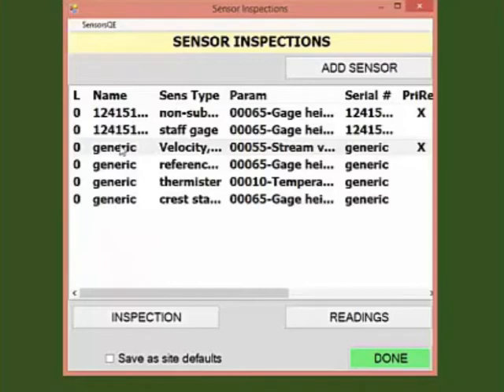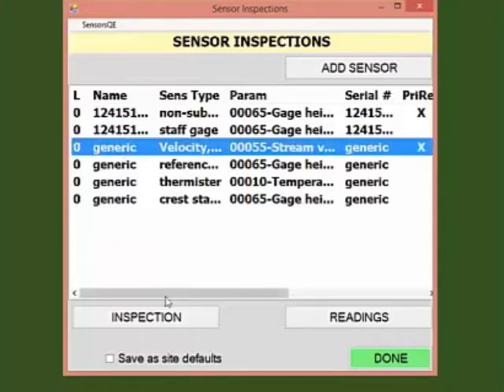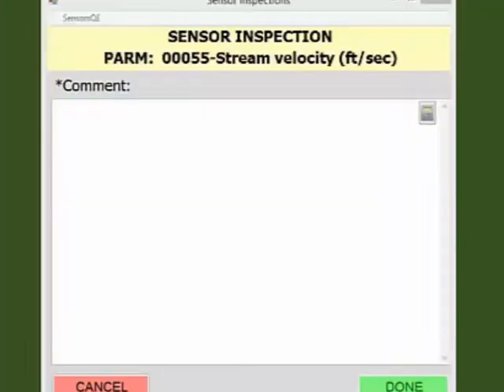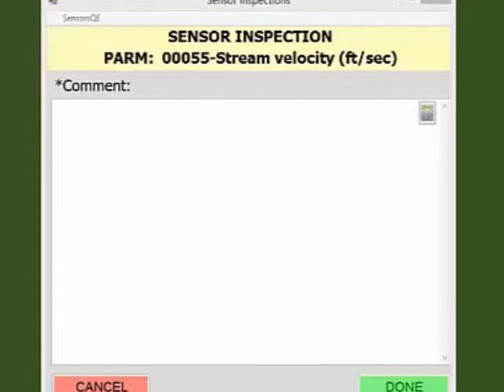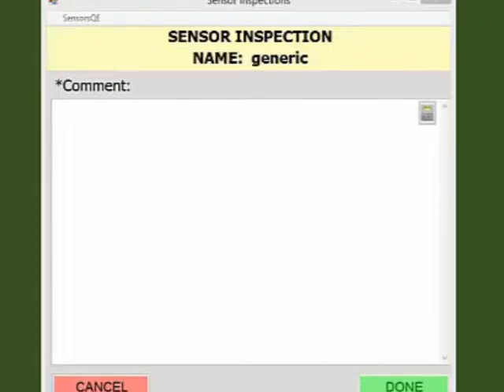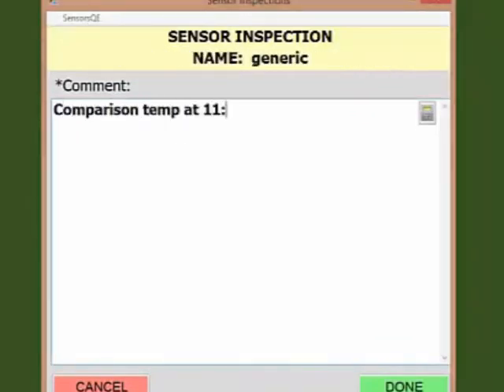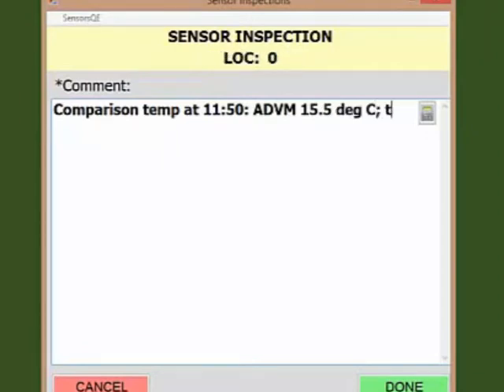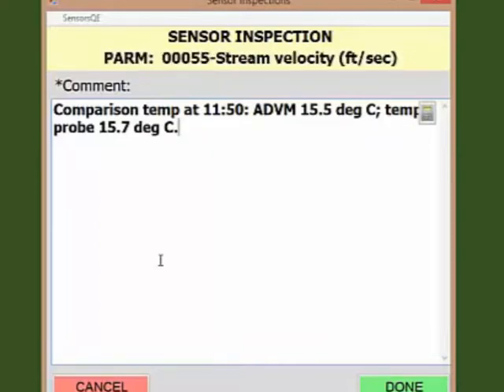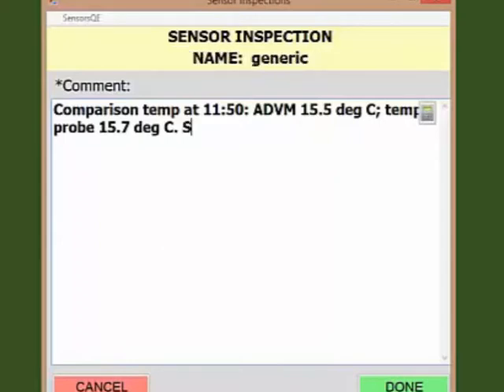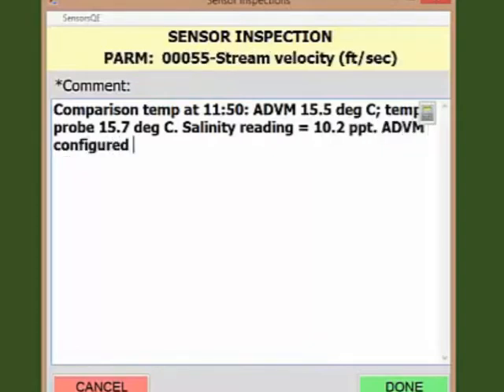Highlight the velocity sensor in the Sensor Inspections table and click Inspection. Per OSW policy, we need to perform a temperature comparison with a thermistor in the ADVM. Let's enter notes about the temperature readings from your ADVM thermistor and a comparison temperature probe. The comparison temperature reading must be made close to your ADVM and the two temperatures must match within 2 degrees C per OSW memo 2010.07. I did my temperature comparison next to the ADVM and I'm going to write: comparison temp at 1150, ADVM 15.5 degrees C, temp probe 15.7 degrees C. If your index velocity stream gauge is in an area affected by salt water, you'll also need to note salinity measurements here. For example, I'm entering: salinity reading equals 10.2 PPT, ADVM configured for 10 PPT.